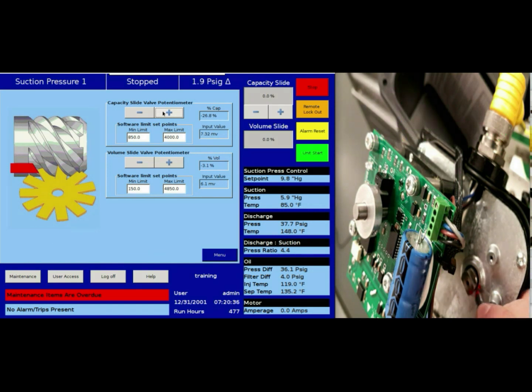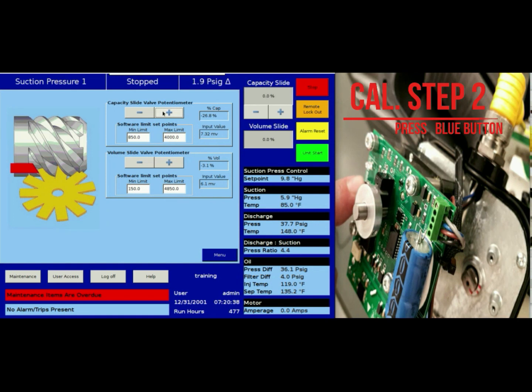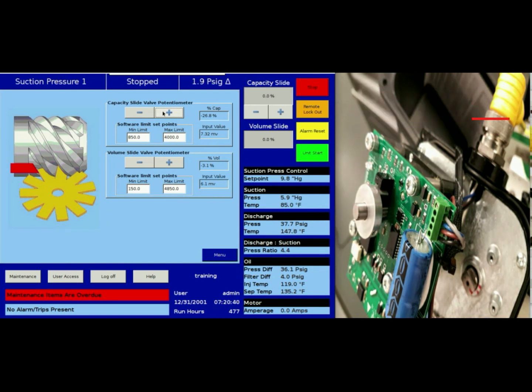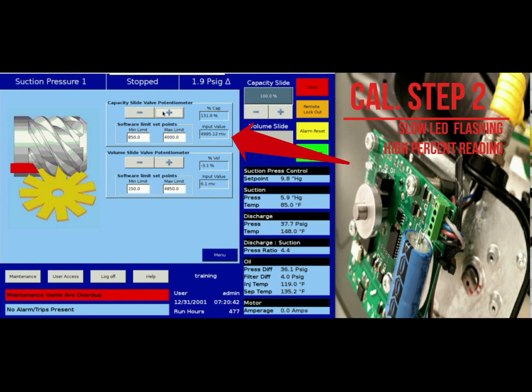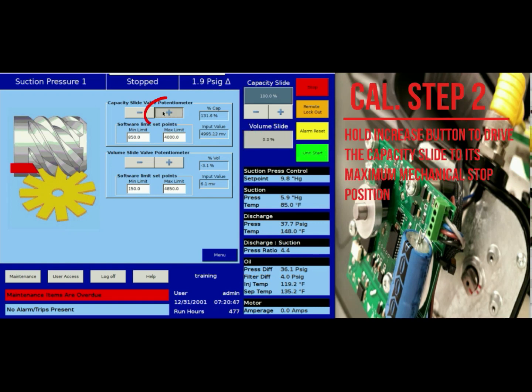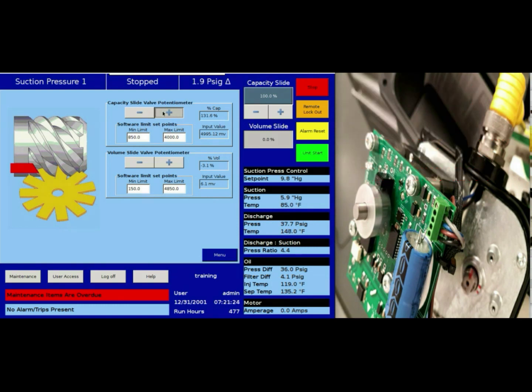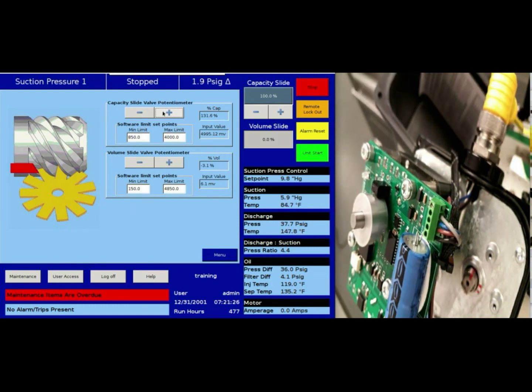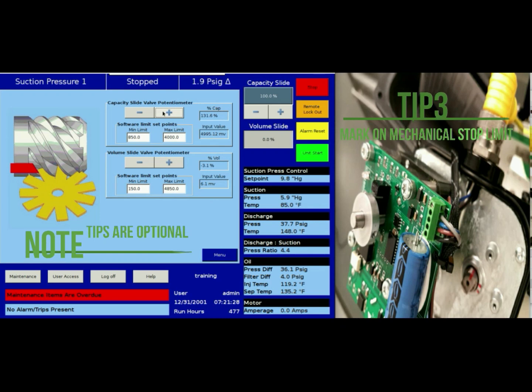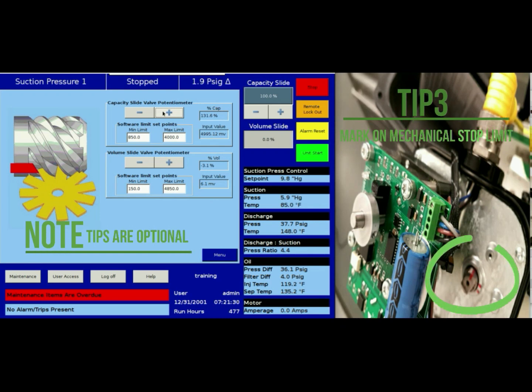Then press the blue button on the actuator one time and you will see the LED light begin to blink slower than in the previous step. You are now ready to set your 100% maximum limit. Press and hold the plus increase button until the actuator has reached its mechanical stop. This can take several seconds, even up to a minute, depends on the size of your compressor. Again, ignore the input value and millivolt reading while calibrating your maximum limit.